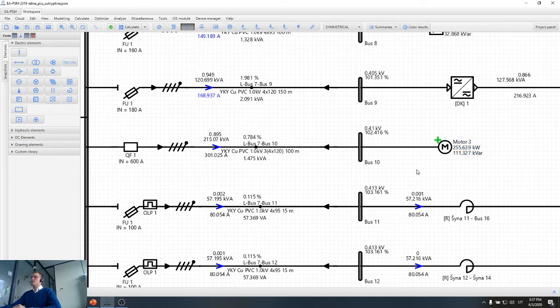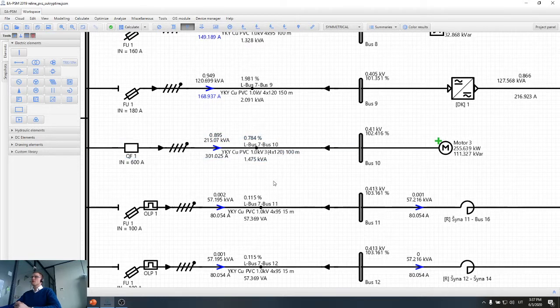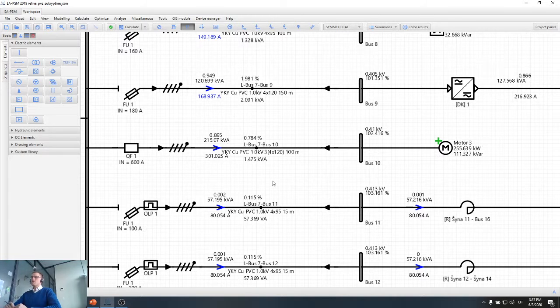However, if a short circuit has already happened either in the motor or in the cable connecting the motor with the network, we still need overcurrent protection devices to disconnect the motor. And a fuse in this case is not allowed and not recommended. Why? Because when a fuse is connected on each phase, there are 3 phases in the electrical network normally. If one phase fuse fails, maybe due to some failure in the fuse itself, it's possible that only one phase fuse will fail.